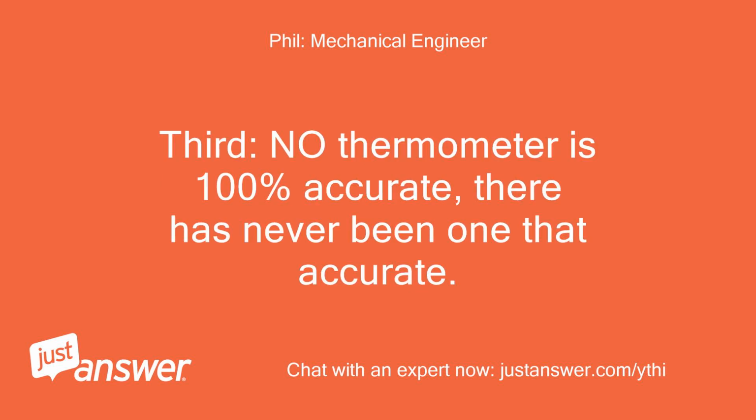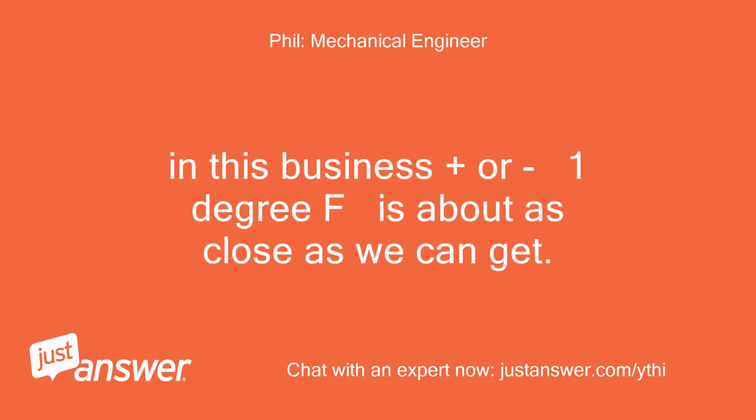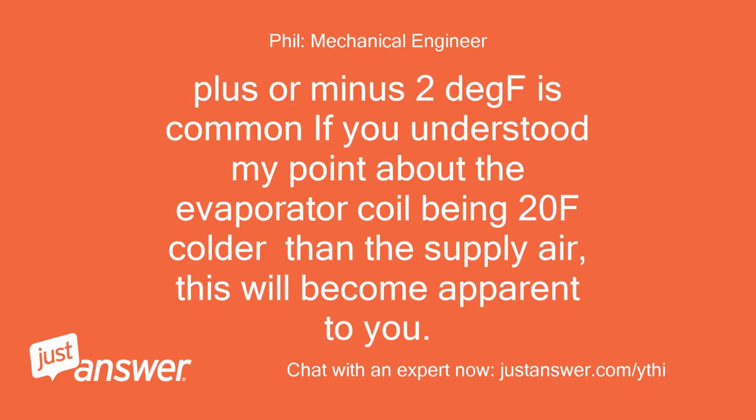Third, no thermometer is 100% accurate. There has never been one that accurate. In this business, plus or minus 1 degree Fahrenheit is about as close as we can get. Plus or minus 2 degrees is common. If you understood my point about the evaporator coil being 20°F colder than the supply air, this will become apparent to you.